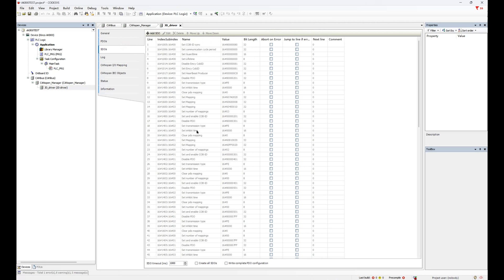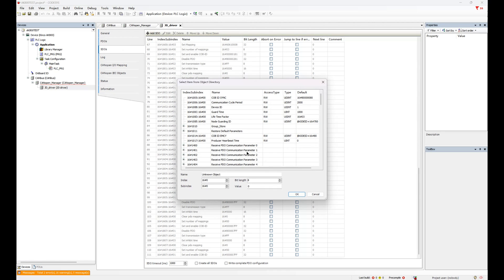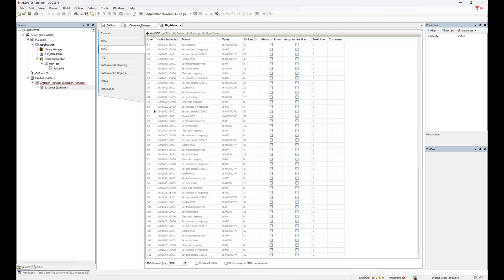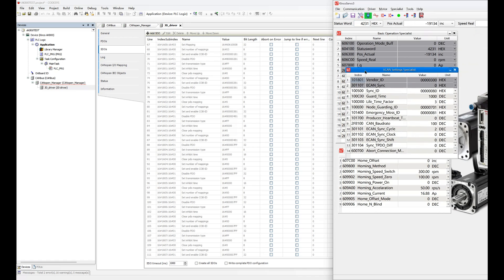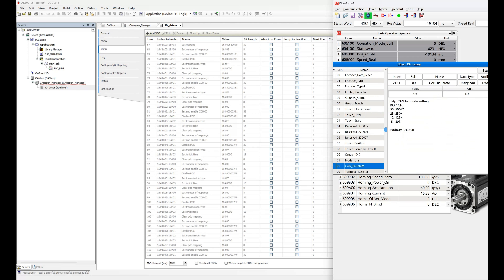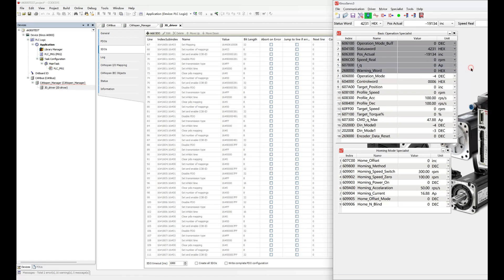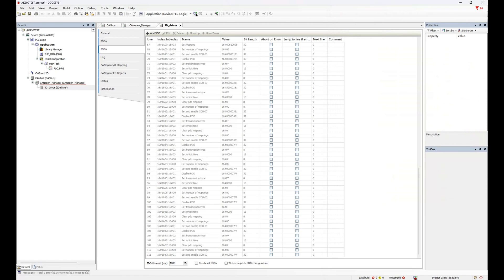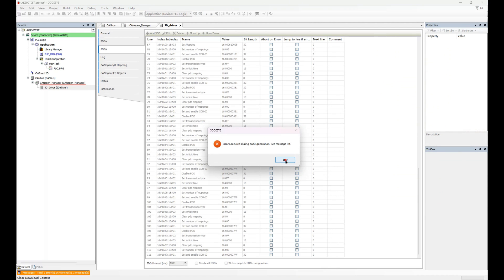In the SDOs, there are some default SDO settings. Users can add additional objects that need to be initialized. In the servo drive, the baud rate and node ID also need to be set. The 100 on the baud rate means using a baud rate of 1000 kbit per second — you can check this from the help. The node ID is defaulted to 1. Then log in to the PLC. If the indicator light turns green, it means the servo is successfully connected.